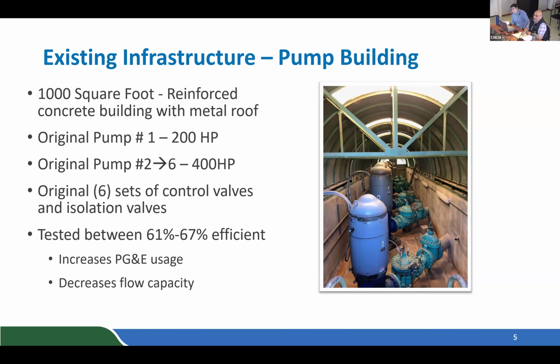Can you just go a little more on what we mean by pump efficiency? Yeah, sure. So over time, you've got impellers within these pumps, and the impellers are made of metal, and they'll break down due to cavitation or just natural wear and tear. So those impellers don't have as much surface area to pump the water as efficiently as possible. So you're actually turning on maybe another pump to pump the same amount of water as you were previously when those pumps were brand new. Just to add a little bit, that equates to adding more energy and more need for electricity at this pump station because of the inefficiencies. So with newer pumps and motors, efficiency goes up, energy consumption goes down.